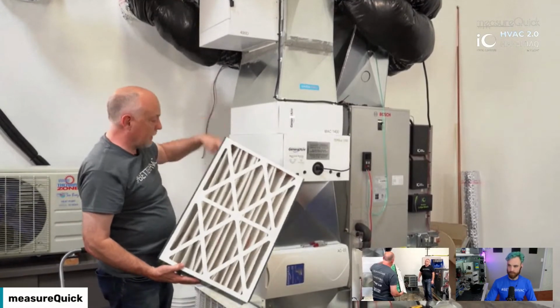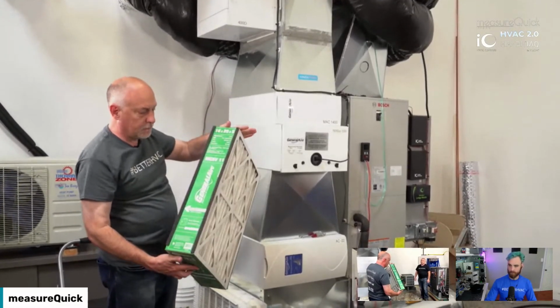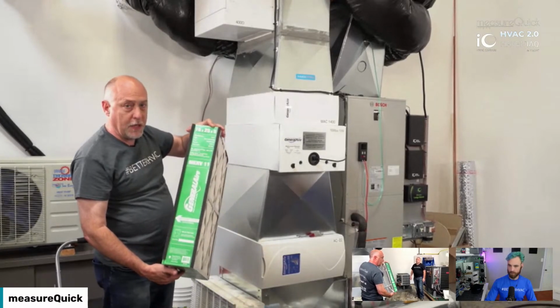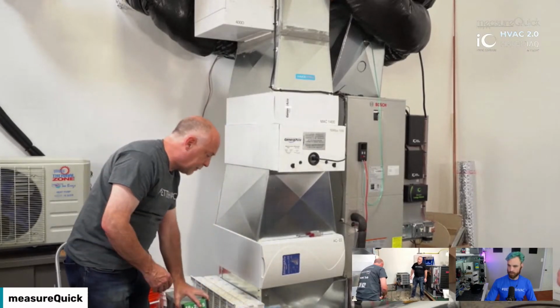So after we baseline with a standard filter, then we're going to try the MERV 11. We'll look at the pressure drops through the filter, and we'll look at how those remove the particulates.